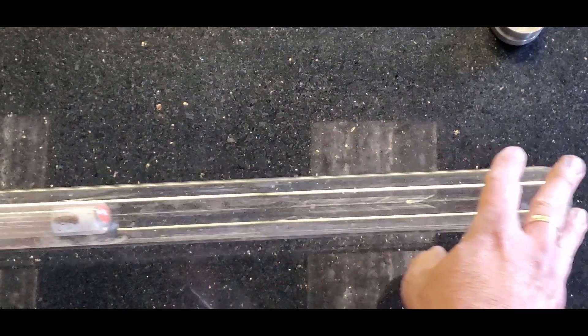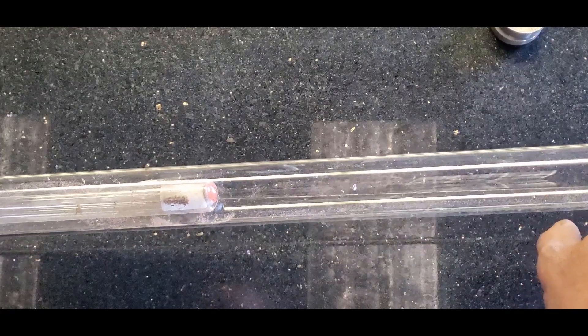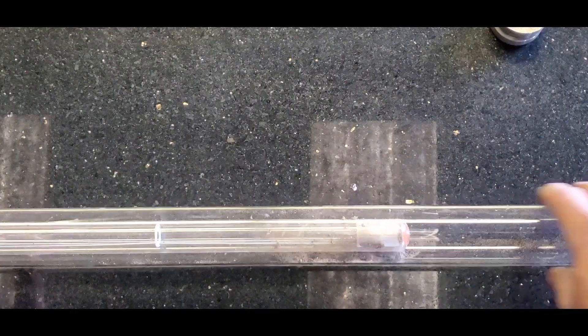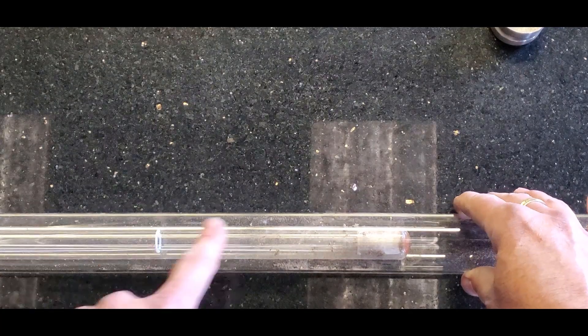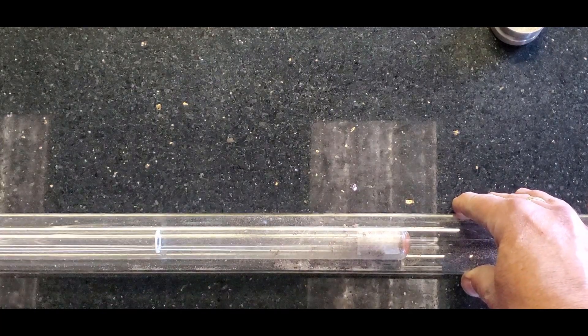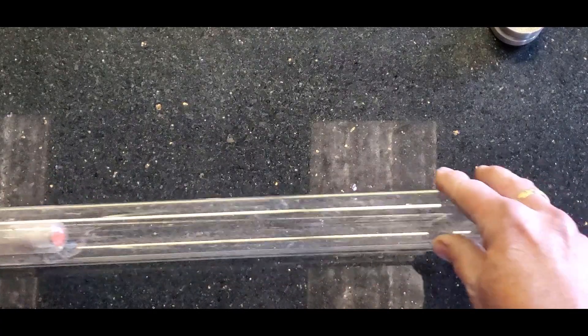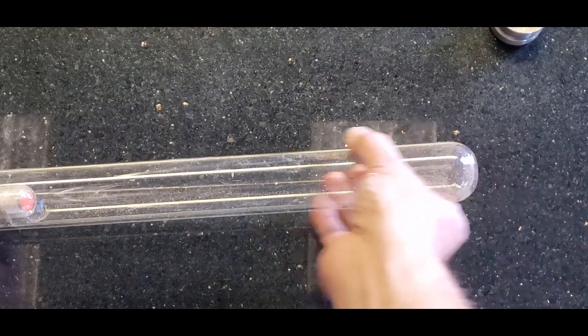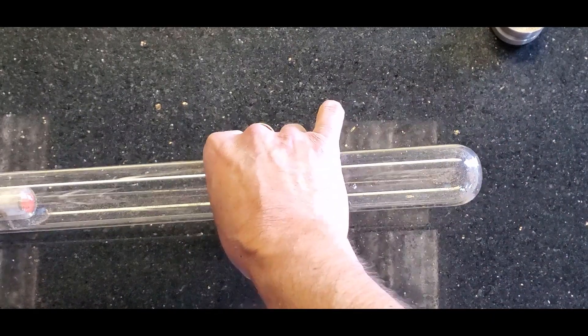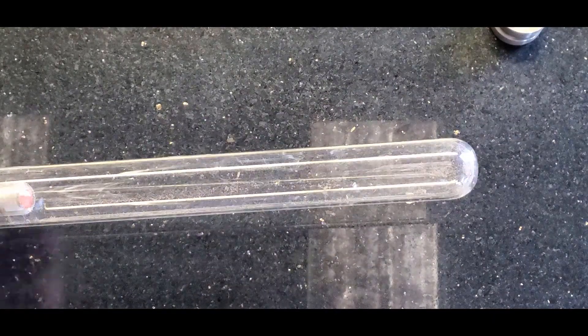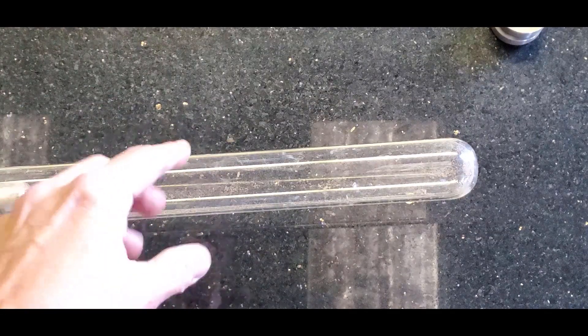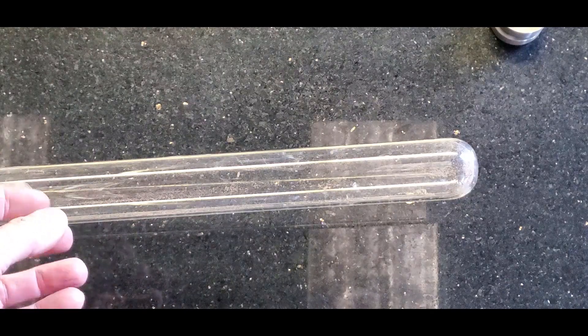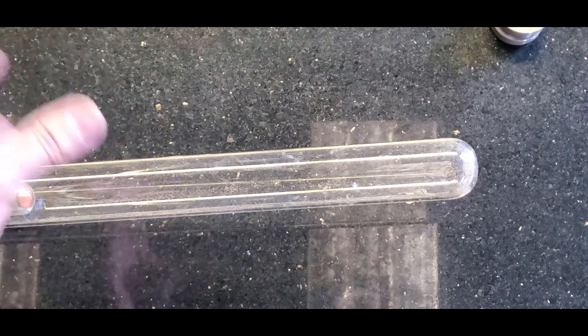There's a lot of different manufacturers of UV disinfectant equipment but they all involve some sort of fluorescent UV light element that's the one that's inside here, and then this tube is actually quartz. It's not glass. They use quartz because with glass and the intensity of this UV light, the glass will actually start to discolor and start to block the ultraviolet radiation from getting out.